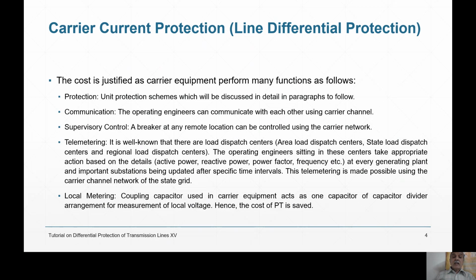Supervisory control. A breaker at any remote location can be controlled using the carrier network. You see, if you want to shed some load and you do not have time, the system is going out of step very fast and you have no time to call another person to shed the load, then you don't call him. You push the button and the breaker somewhere trips. You push the button at Ahmedabad and the breaker at Surat trips. You push the button at Delhi and the breaker at Lucknow trips. That remote control is possible using this carrier current protection.